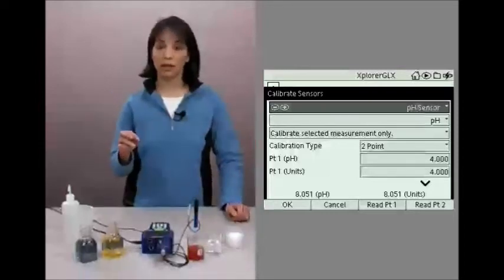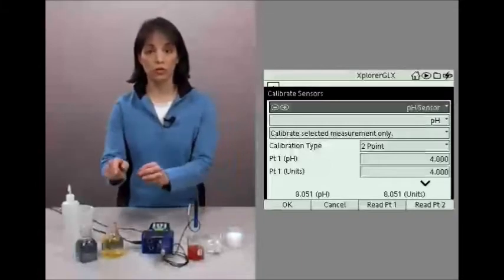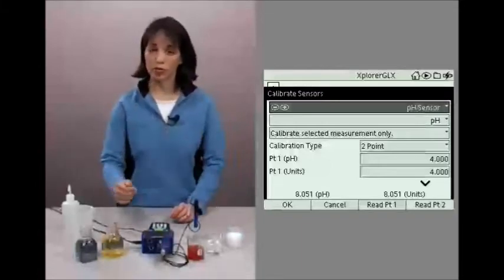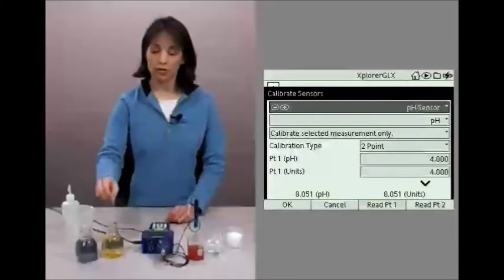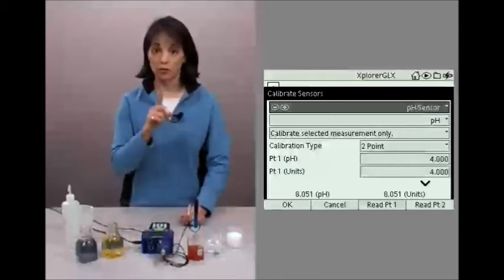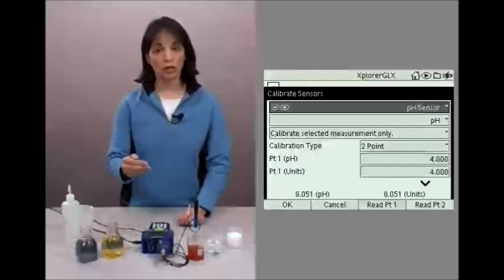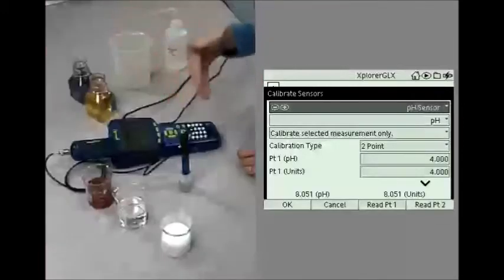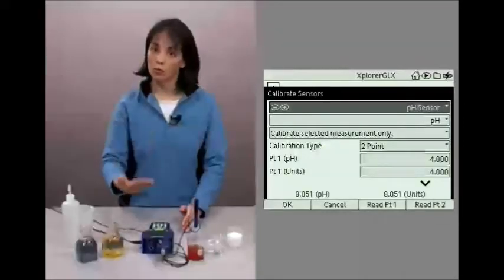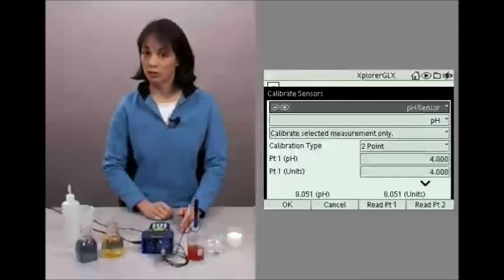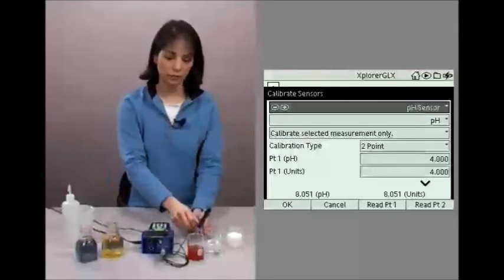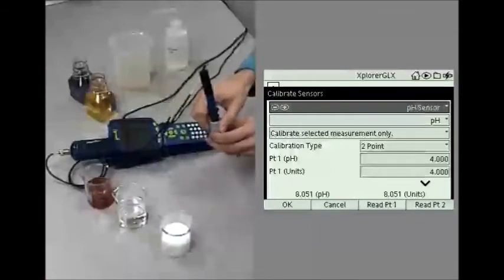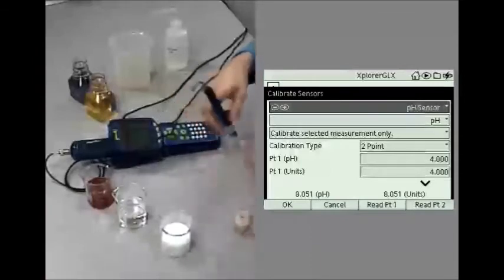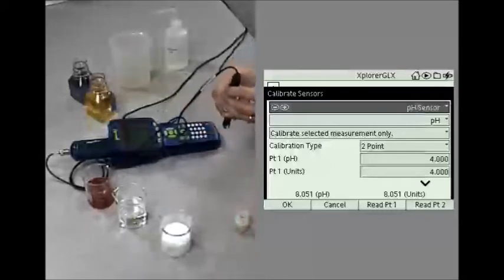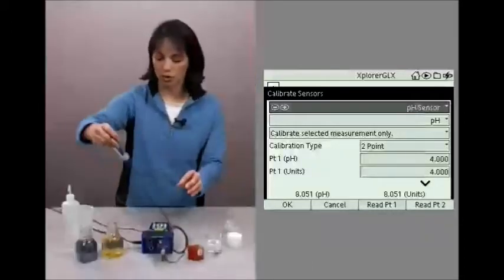Now, during a 2-point calibration, you put the sensor in the first of 2 standards. We are using buffer solutions, one at pH 4 and the other at pH 10. So you put the sensor probe into the first of the 2 solutions and tell the Xplorer GLX to read the raw value from the sensor and report it as the known value of the standard. Let me show you what I mean. Let's go ahead and take this and put it into our first solution. And then I'm going to have you, actually let's hold on to this right here.